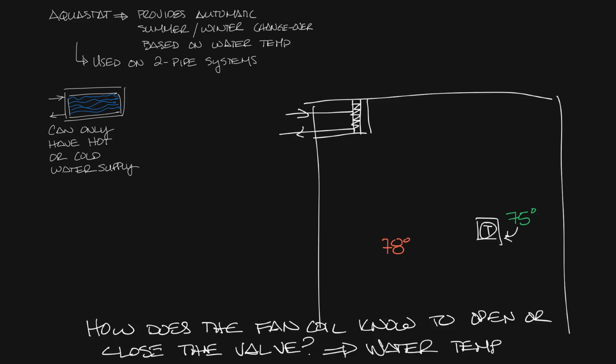If the fan coil has cold water, you want to open the valve to provide more cooling to the space. But if the fan coil has hot water coming to it, you want to close the valve because the space is already too warm.